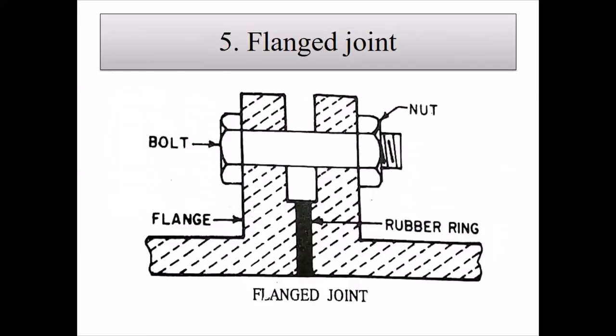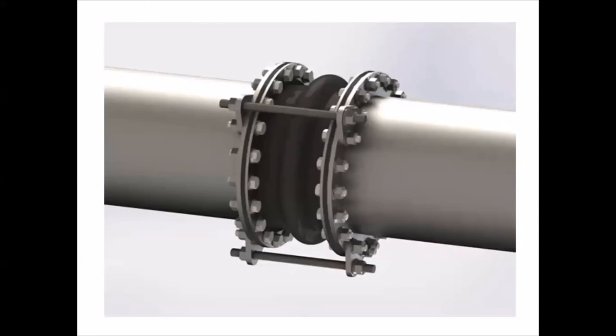The flange joint is recommended for temporary work where the pipeline may be dismantled or shifted after use. The end of the pipe is provided with a wide flange with several holes for nuts and bolts. When joining, a rubber gasket is inserted between the flanges and the nuts are tightened to make the joint watertight.